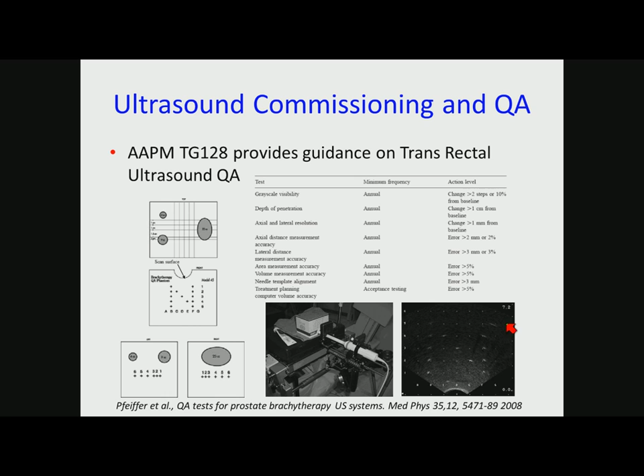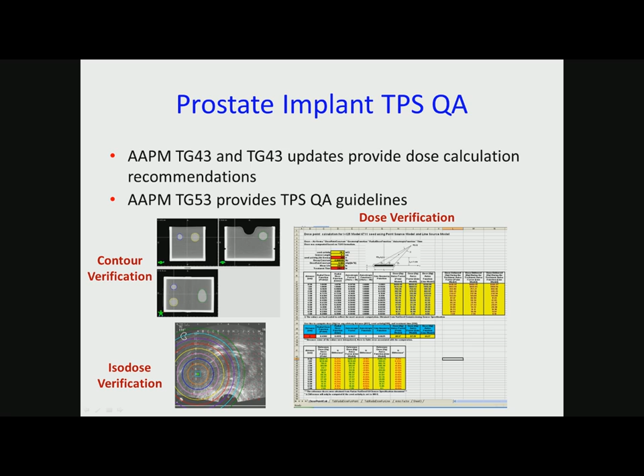For the treatment planning system, you can have a Symphony, a VariSeed, some of the bigger brachytherapy prostate implant treatment planning systems. What you do is you scan the phantom, and then you can also try to contour the phantom to look at the contours to make sure the anatomy is correct. You can do some isodose verification, and you can do an Excel spreadsheet sitting in your office. Put a seed in there, look at the dose at a certain point. You can do this with one or two source locations, but once you go more, it gets a little bit more complicated. But this is a verification, an independent check of the treatment planning system.